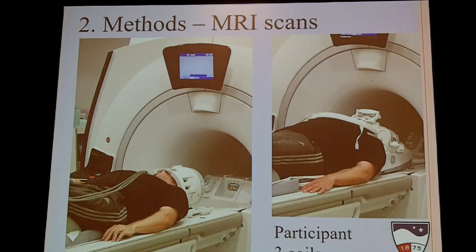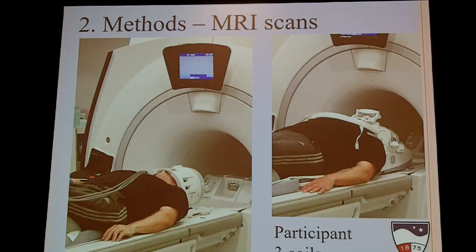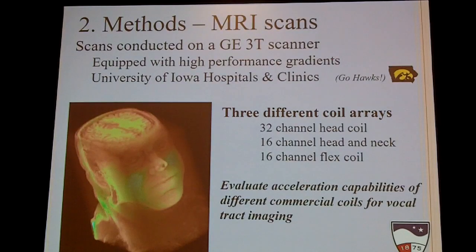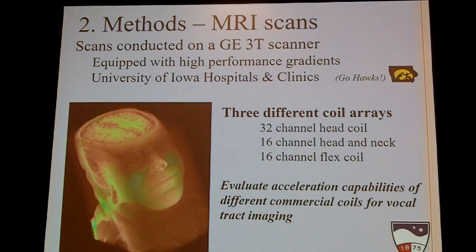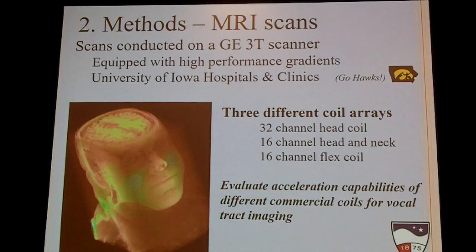We had one participant — whose voice I'm very familiar with — get scans in October and also earlier this month at the University of Iowa. That's me. We tested three commercially available coils for vocal tract imaging. The scans were conducted on a GE 3T scanner equipped with high-performance gradients at the University of Iowa Hospital. We tested a 32-channel head array, a 16-channel head and neck coil, and a 16-channel flex coil to evaluate their acceleration capabilities.